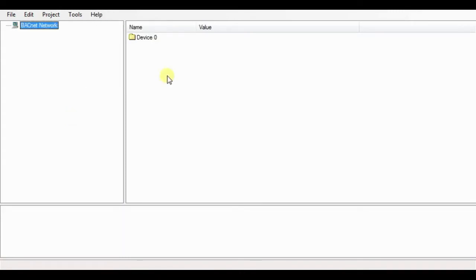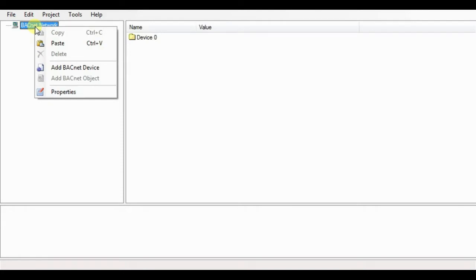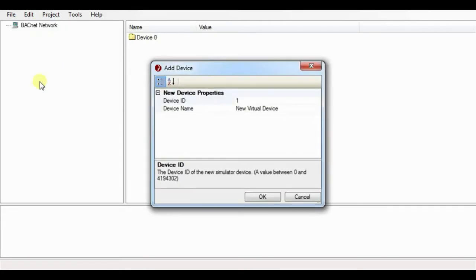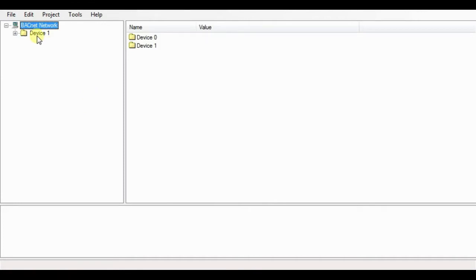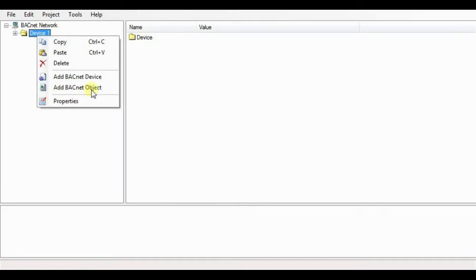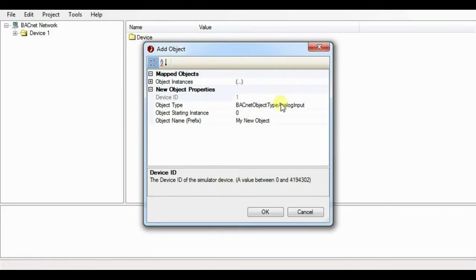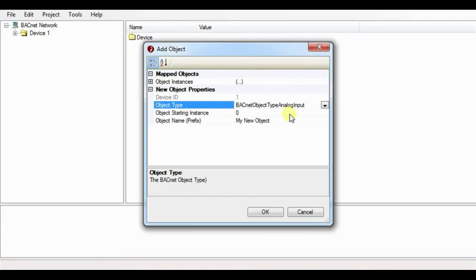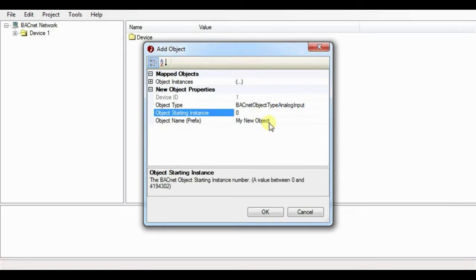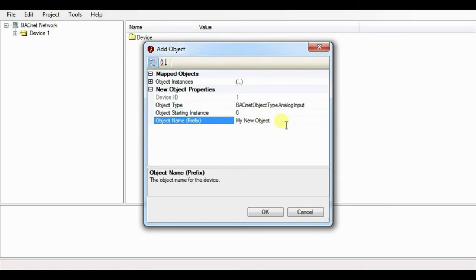This is the main window of what the BACnet device simulator looks like. Any BACnet device must contain a device object. The device object defines a standardized object whose properties represent the externally visible characteristics of a BACnet device. There shall be exactly one device object in each device. To create a device object, right-click on a BACnet network and select the BACnet device. You can change the device ID and its name as per your requirement. To create different objects, right-click on the device and select Add BACnet Object.